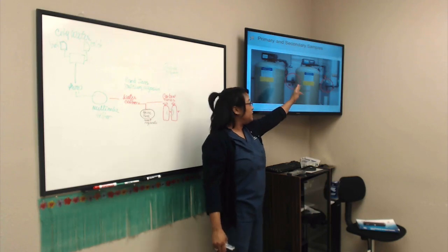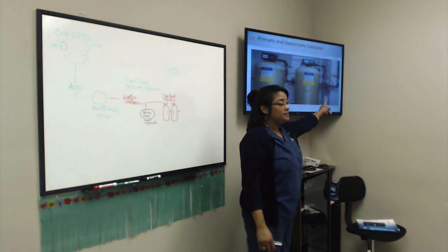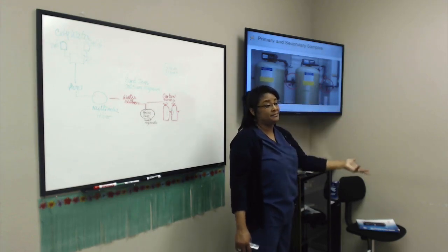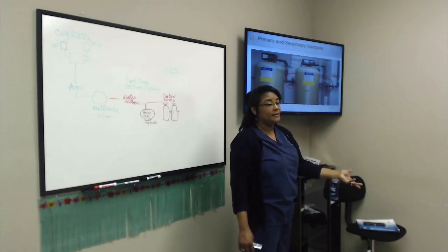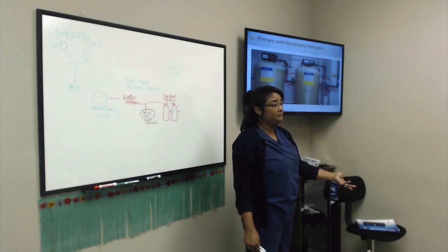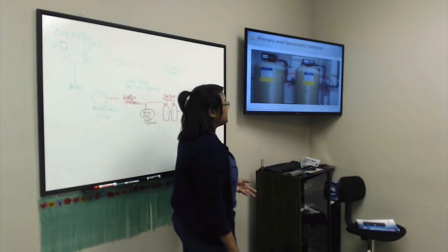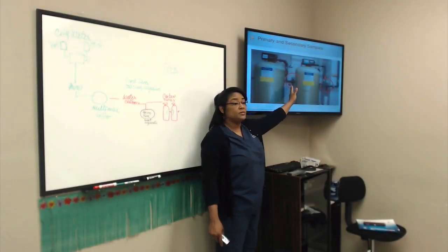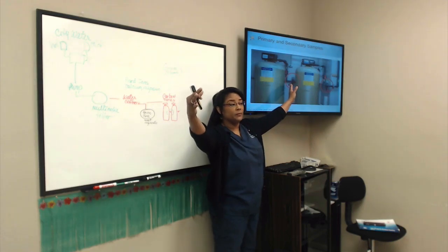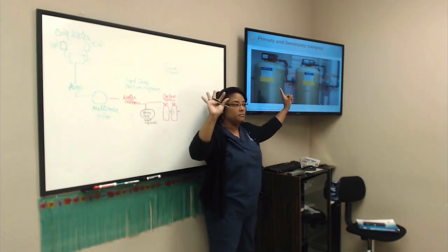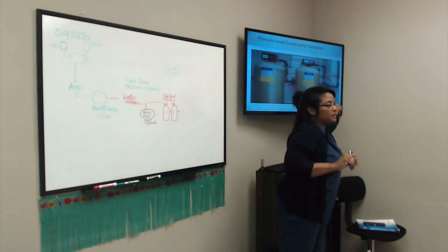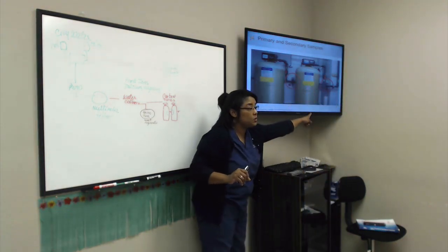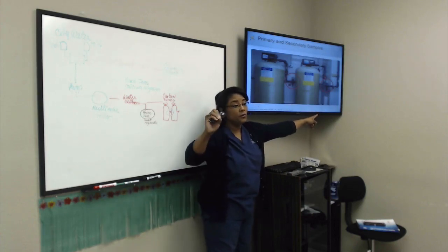If it's okay, we don't have to retest. Once the first one is okay, the second one would be for retesting. Let's say I do this one, and the result is above 0.1. So we say, wait a minute, let me test again. And when we test after the second tank, if that one is okay, then we are good to perform dialysis.